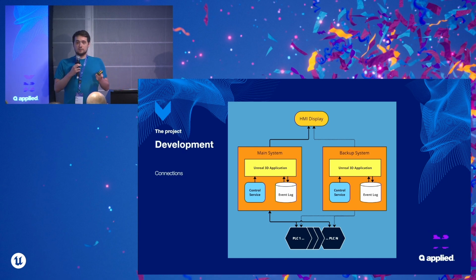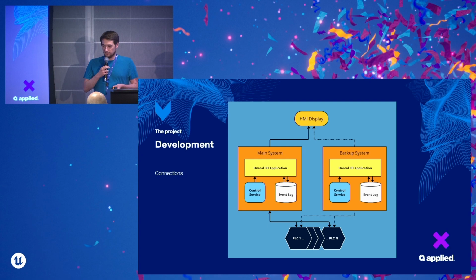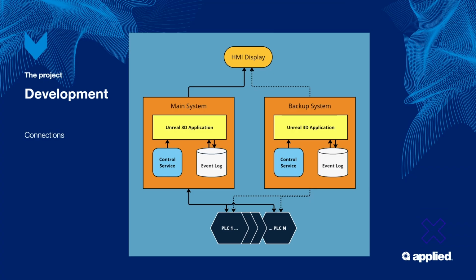And the other one, which is the most critical, is the write information. Like if the captain changes a variable, they will want the variable to be actually changed, so we can't afford to have errors on that part. So these two connections talk with Python, and Python has basically two main threads. The first thread handles the gathering of the information from all the other threads that talk to the PLCs, and another thread is just to handle the write data, because that was very important.